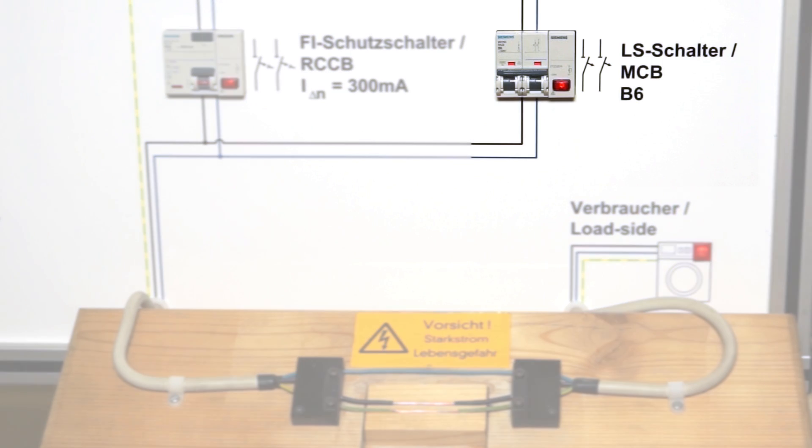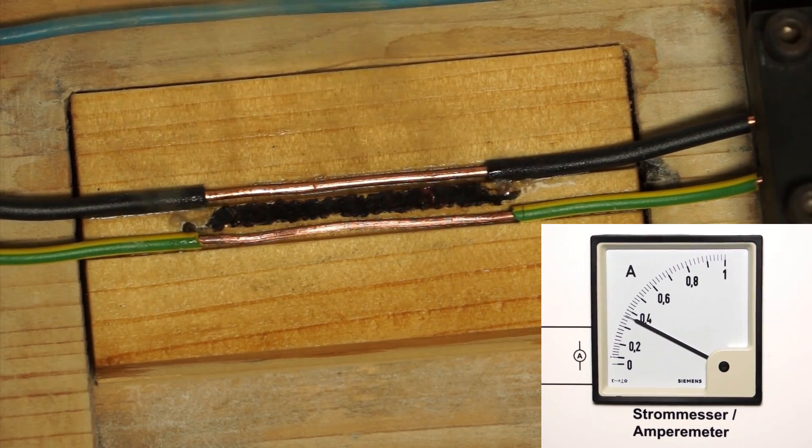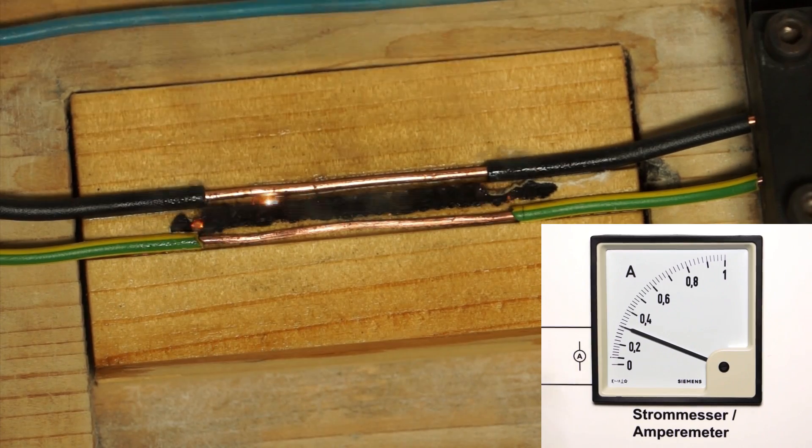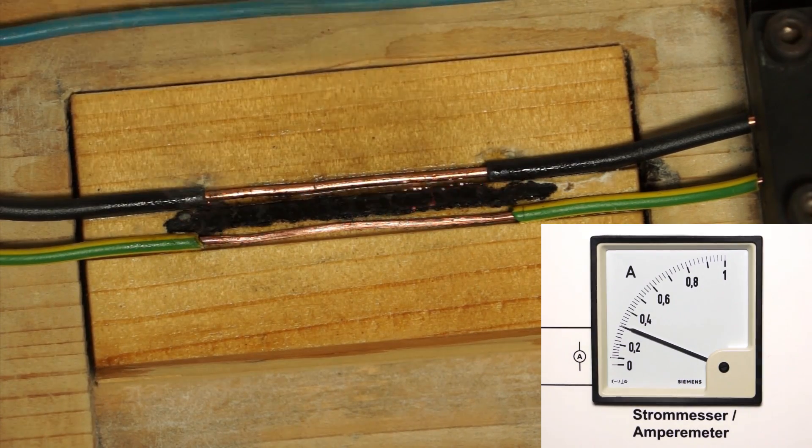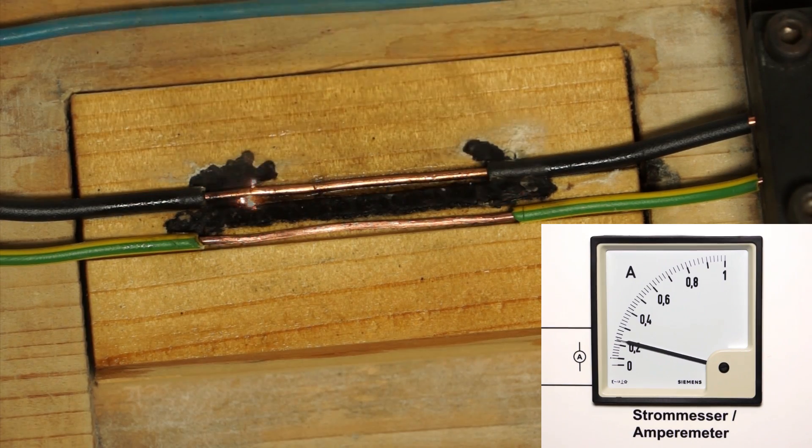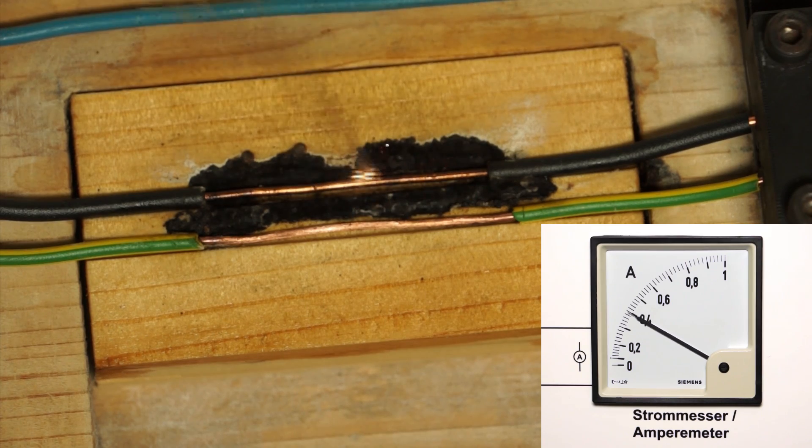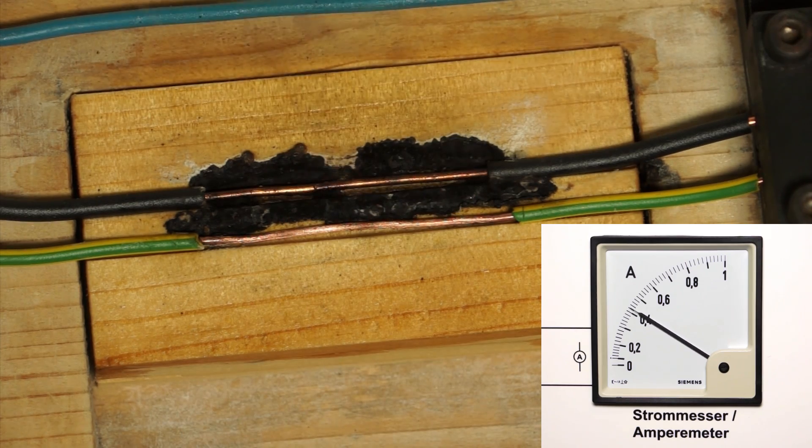In this case, a miniature circuit breaker cannot protect against electrically ignited fires as it only trips at much higher currents. The insulation fault simulated here can easily lead to a smoldering fire or even a full blaze. RCCBs with a rated residual current of less than 300 milliampere could prevent this fire and consequently provide preventive fire protection.